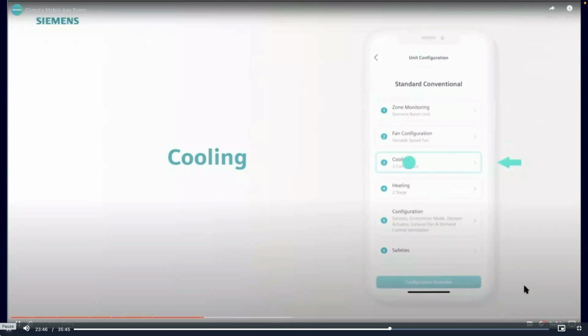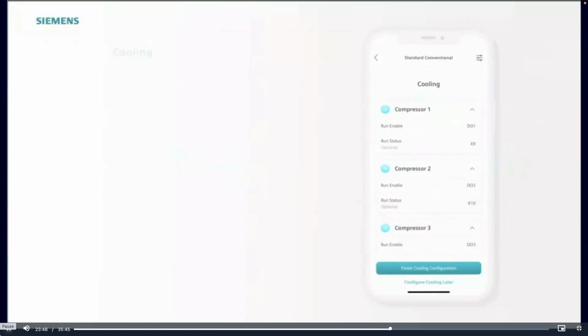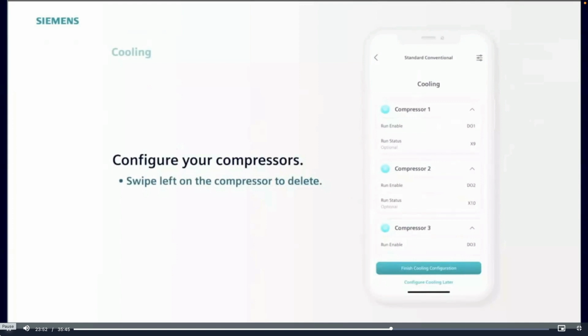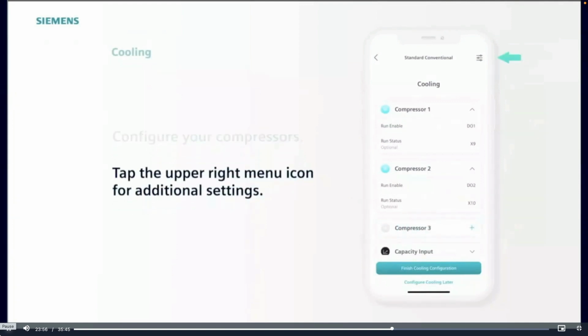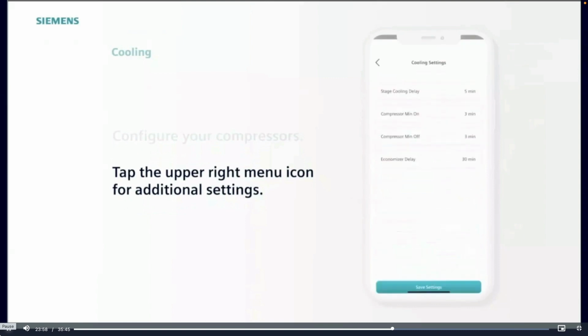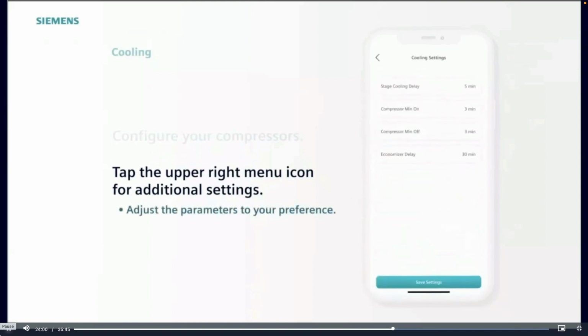Step 3 is cooling. There are 3 cooling compressors configured. If you only have 2 stages, you can remove one by swiping left to delete. Next, select the menu icon at the top right. Here, you can select the duration of the on delay, minimum on and minimum off delay, as well as economizer delay in case you want your compressors to overlap a little with economization. The default settings will work for most cases, adjust as needed, and then select Save Settings.